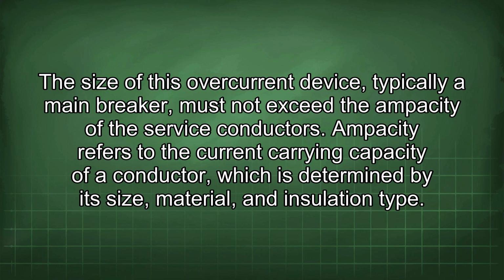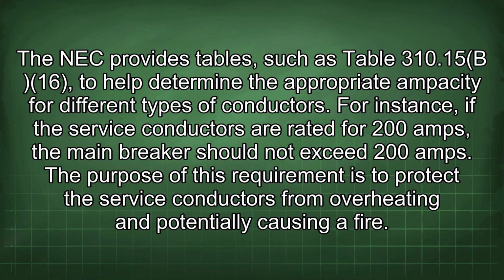The size of this overcurrent device, typically a main breaker, must not exceed the ampacity of the service conductors. Ampacity refers to the current carrying capacity of a conductor, which is determined by its size, material, and insulation type. The NEC provides tables, such as Table 310.15(B)(16), to help determine the appropriate ampacity for different types of conductors. For instance, if the service conductors are rated for 200 amps, the main breaker should not exceed 200 amps. The purpose of this requirement is to protect the service conductors from overheating and potentially causing a fire.